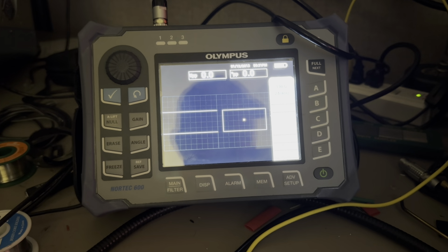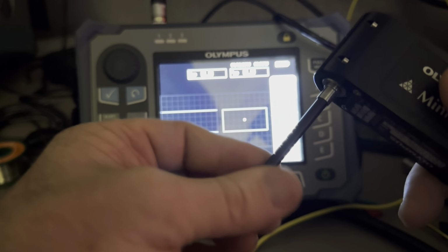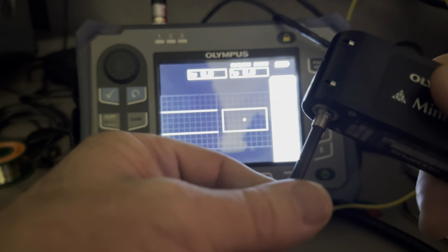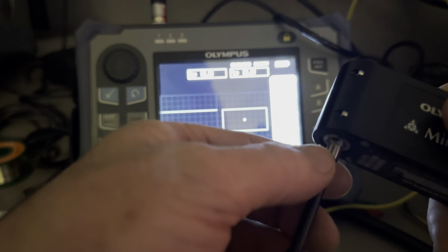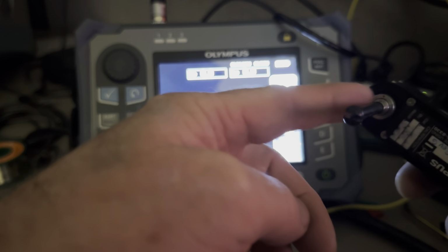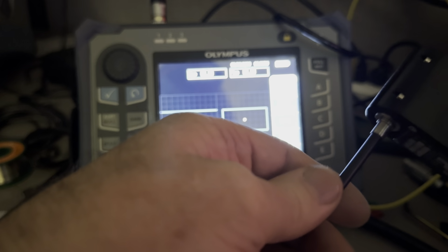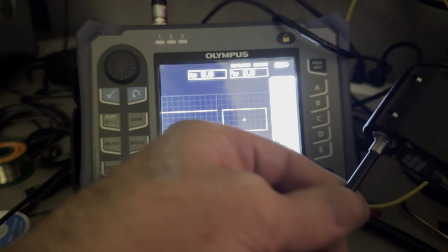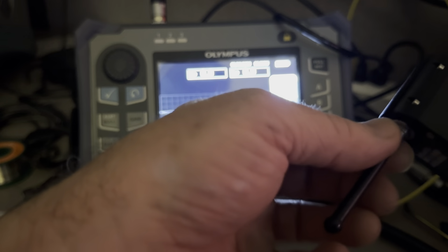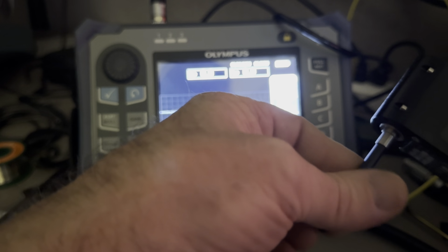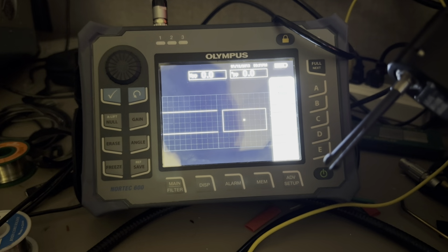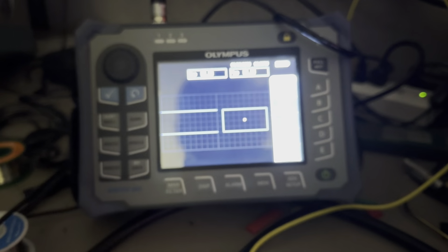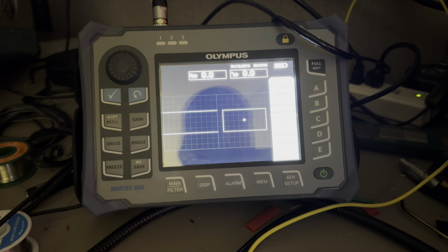Now the same kind of thing. I'm going to look at my probe. And this one, does it have a line on it? The line on this one's actually up on the base of the probe. There's a little dot and there's a little red line. And you also want to line that dot and line up with the little red mark on the opening to the scanner. That way you'll align your pin receiver so you don't bend the pins. Because you know that you don't want to wreck your scanner and the probes aren't super cheap either. So keep them lined up. You might want to put a little dielectric grease on there. Because if you don't, it can be hard to pull this probe back out. So keep it nice and lubricated with some dielectric grease, and that'll extend the life of probably your scanner and your probe. So I just need to take my EDM block, and my tester's already on.